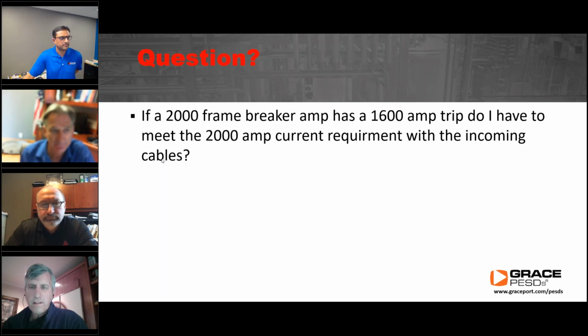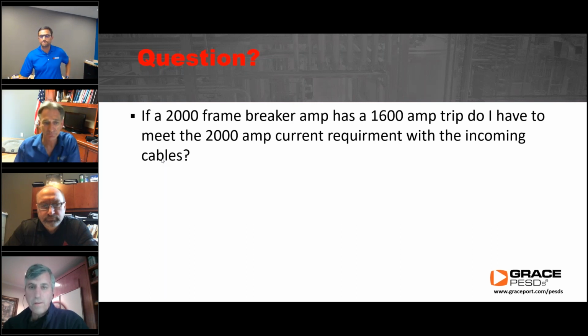I'd like to toss one other thing in there too, just from the engineering side, is that we have to size the conductors not only for the thermal damage limits, but also withstand as well. So short circuit current and clearing time need to be taken into account as well. So it may be that you have larger conductors just because of the clearing time or the withstand rating is what I'm getting at. So that's the other side of the equation. I agree with everything Charlie said. I just thought I'd toss that in there about the other reason we engineer the conductor sizing.